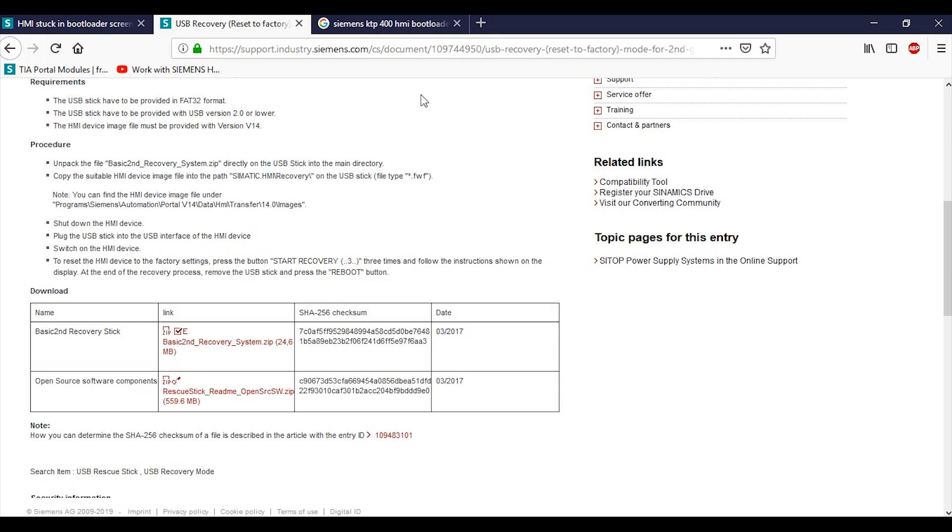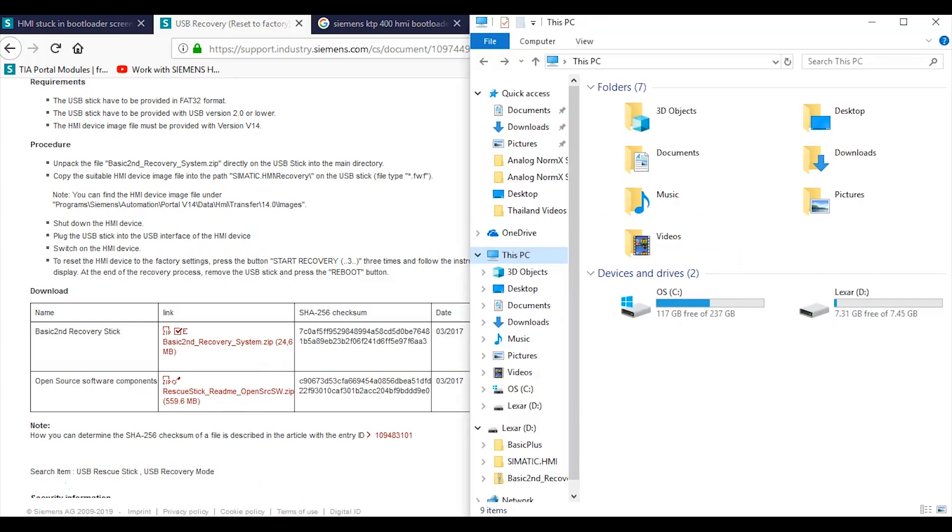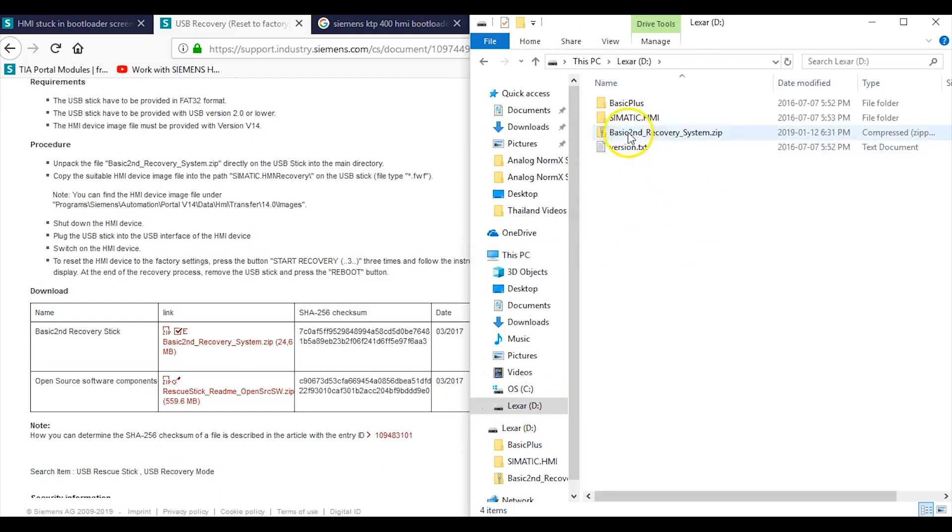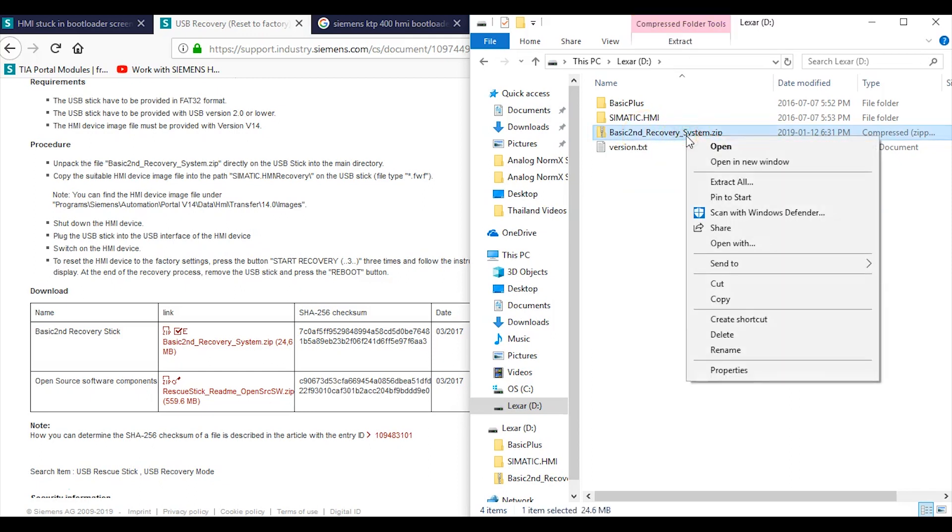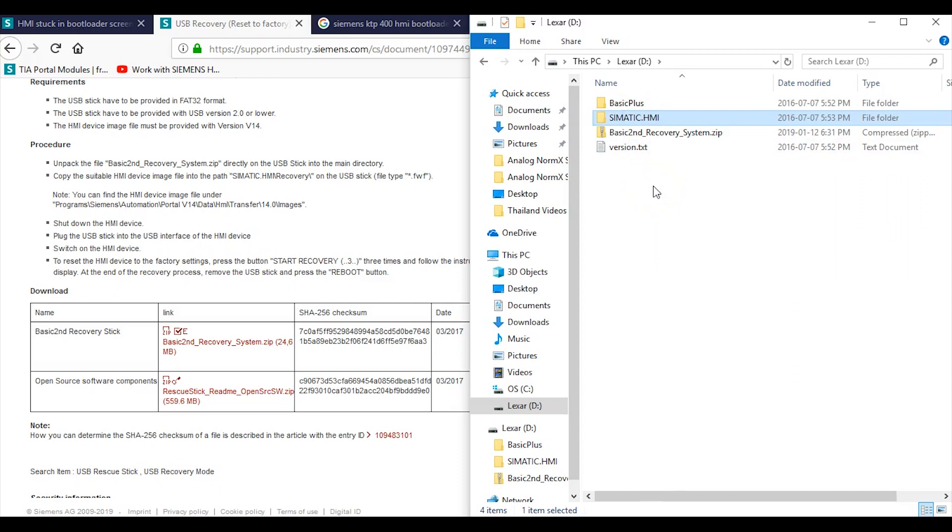It says unpack the basic second recovery system zip directly onto the USB in the main directory. Copy the suitable HMI device image file onto the path Simatic HMI Recovery onto the USB stick, file type FWF. First thing you need to do is download the basic second recovery system zip file to your USB stick. Again, my USB stick is right here. I have downloaded Basic Second Recovery System, and then you just go like this and extract all. You will have two files: Basic Plus and Simatic.HMI.